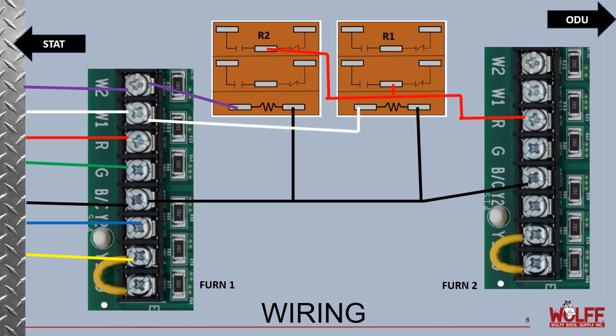Next, we're going to bring R from furnace 2 over to one side of the normally open contacts on both relays. And then we're going to complete that by bringing W1 to the opposite side of the normally open contacts on relay 1. And relay 2 is going to connect through to W2 on furnace 2.